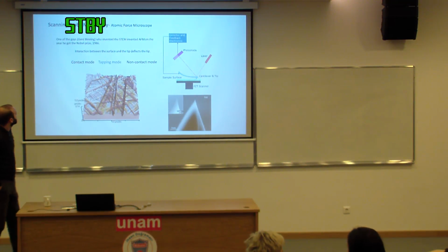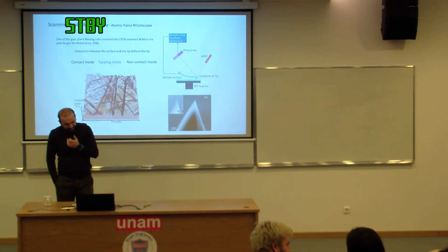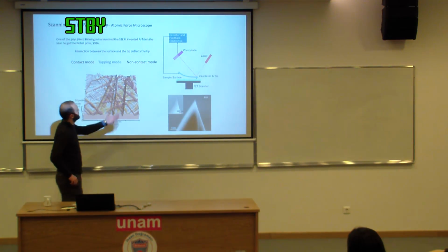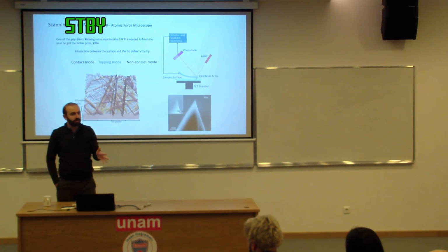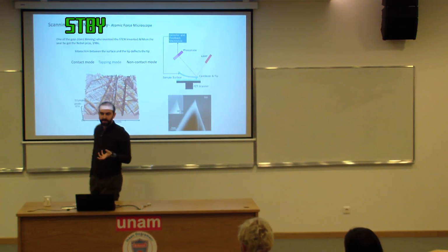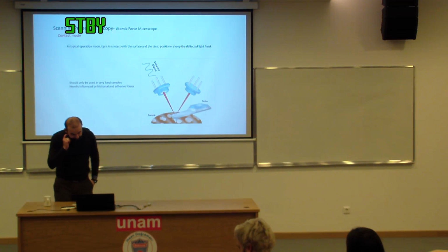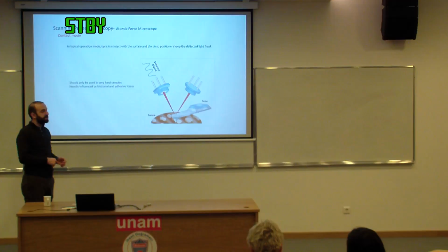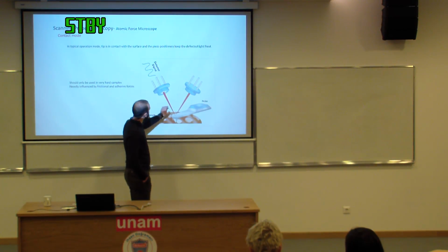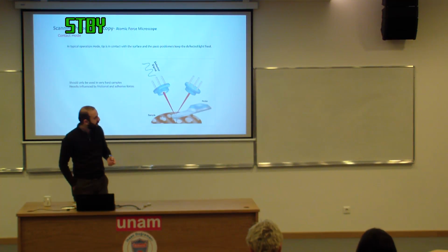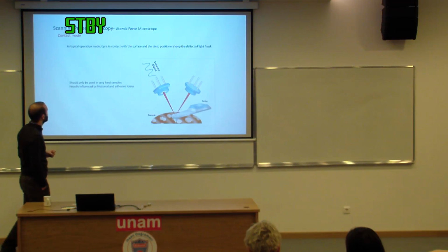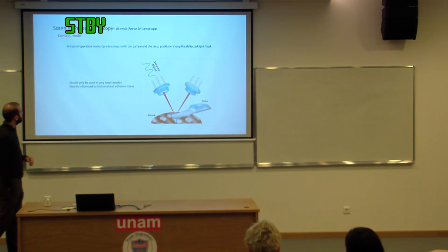Whatever. There are three different modes: contact mode, tapping mode, and non-contact mode. Of course, these drawings oversimplify things, but there are many complications when you actually look at the real thing. First of all, this is an extremely noisy measurement. So what you do is you vibrate the probe at a certain frequency. You drive it at a resonant frequency. Since you know that frequency, your signal is modulated at that frequency, and you use that information to infer how much deflection you get using lock-in techniques. I'll talk about that in more detail, but this is typically how it works.